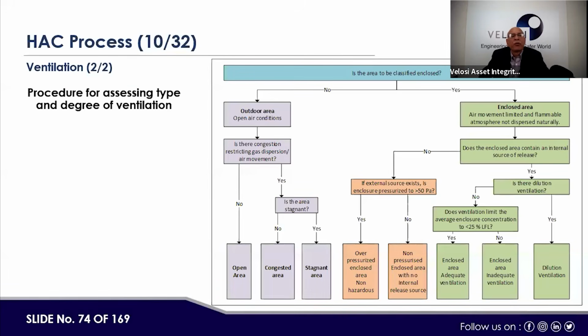So here is the procedure for assigning the type and degree of ventilation. First is the outdoor case. In outdoor, we ask: is there congestion restricting gas dispersion or air movement? If no, it is an open area. If yes, then is it a stagnant or congested area? Accordingly, the ventilation system is defined.